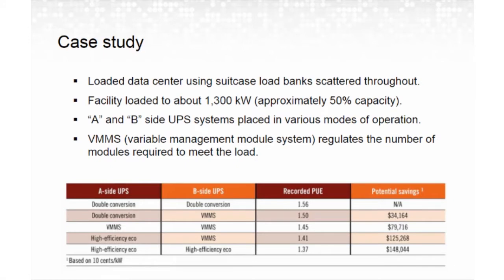So for the case study, we basically loaded up the data center with load banks scattered throughout. The facility was loaded to about 1,300 kW, about 50% capacity. The A and the B systems were placed into various modes of operation. So we started out with the A side and the B side, mostly going through double conversion, recorded a 1.56 PUE.